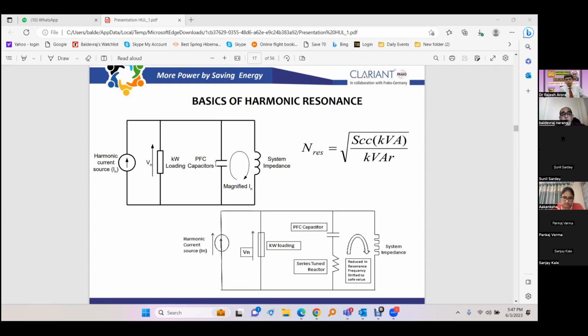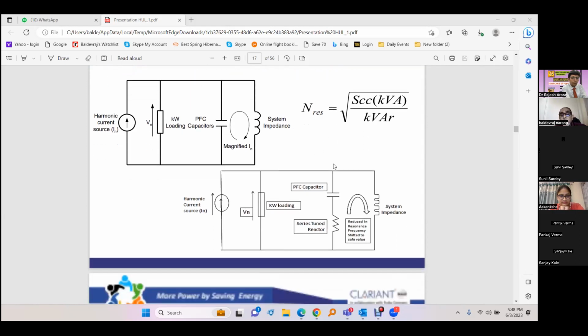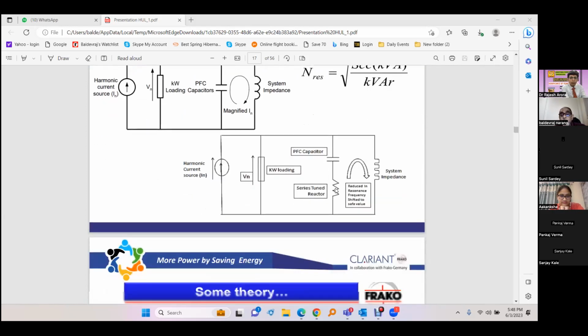And another problem is that because this L and C are in parallel, they have a resonance condition at some point, and this resonance condition may occur at a harmonic frequency, and that harmonic will get amplified. So that is another problem. So what we do is we don't use plain capacitors. We use capacitors in series with a reactor, a series reactor. So what it does is it does 2-3 jobs.